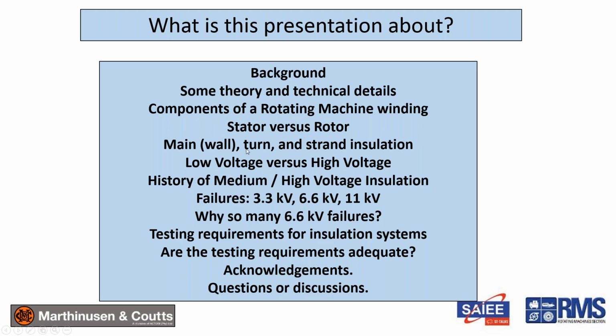Then we delve into it a little bit deeper in terms of main wall insulation, turn insulation, and strand insulation. This presentation is specifically about main wall insulation of medium voltage. I often refer to it as high voltage in the presentation because medium and high voltage are interchanged between Europe and the US, between machines and switchgear and transformers. So I'm talking about 3.3, 6.6, and 11 kV. History: I actually realized about half an hour ago that I left out a slide on this. All it is is a graph of how the average main insulation has decreased in thickness over the years. So that's what it shows.